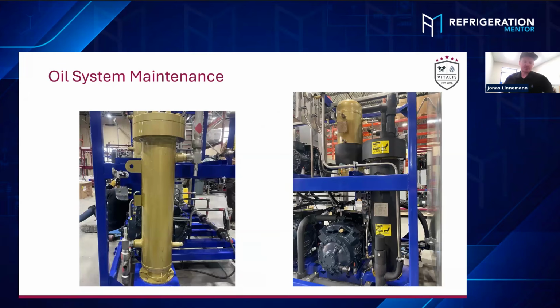And I've taken some pictures out of the production to see a little more clearly how the arrangement of such an oil separator actually is. So here on the right picture, you can see this little tiny oil return line goes into that solenoid strainer block. And here the level switch will be installed. And this level switch then activates that solenoid and returns the oil into that reservoir.